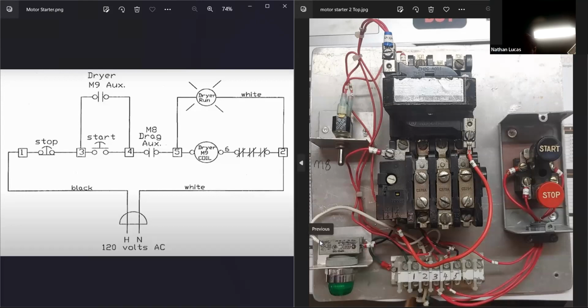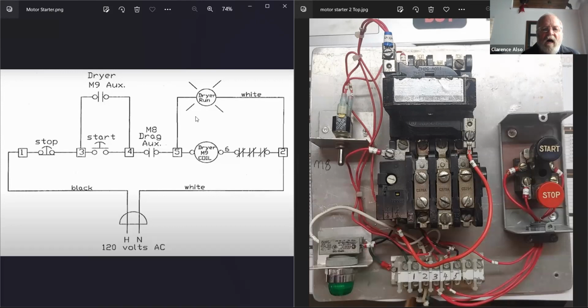Hey, so you cut out, I didn't hear you. Okay, so I'm telling you that you have 120 volts here and 0 volts right there. Is that a good reading or a bad reading? That would be a good reading. Okay, if you had a good reading on both sides and my light doesn't come on, what does that tell you? That your light bulb's probably bad.